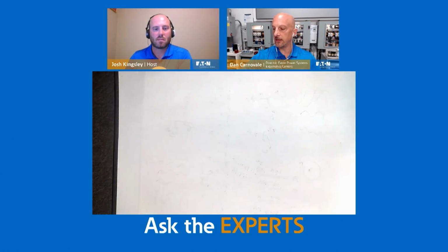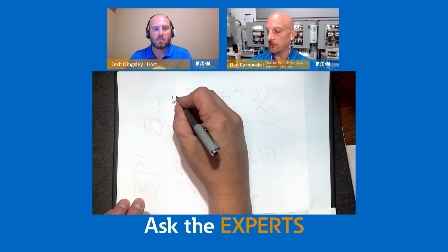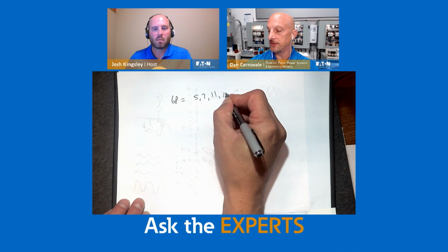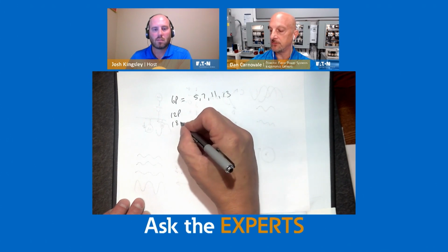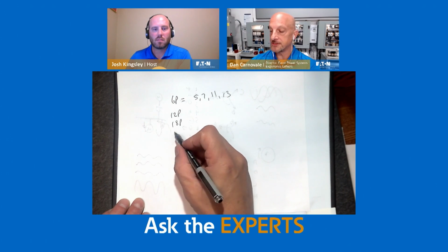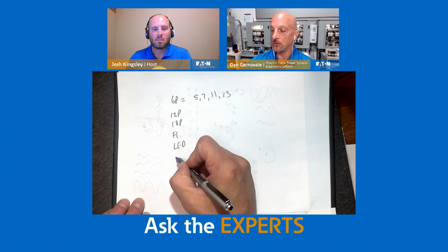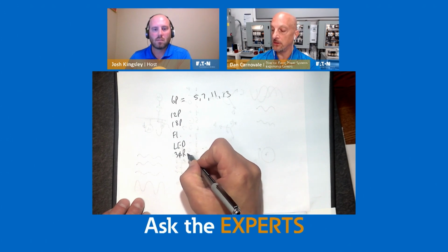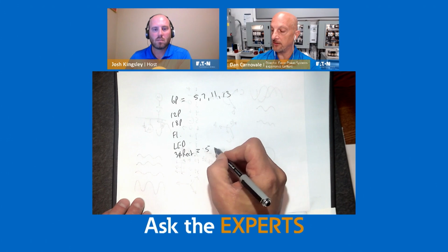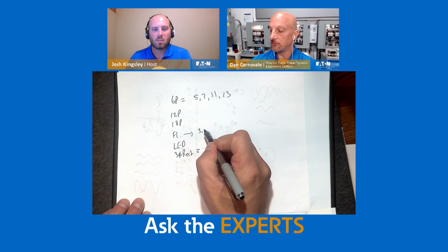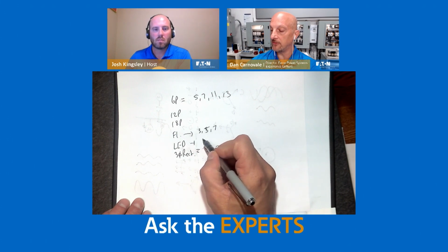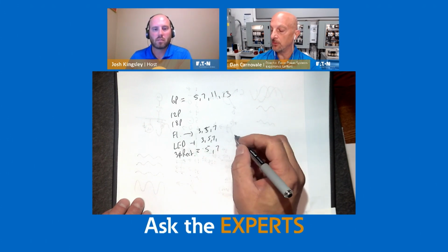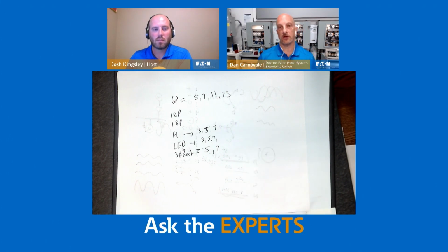And if you look at VFDs, we say six pulse, we already said fifth, seventh, 11th, 13th, 12 pulse, we could figure that out, 18 pulse, we could figure that out. But fluorescent lights or LEDs or maybe a three-phase rectifier for vehicle charging, for example, might have fifth, seventh, whatever. This might have third, fifth, seventh. LEDs might have third, fifth, seventh, but they might be a different spectrum, a different pattern. The nice thing about harmonics is they're pretty predictable in terms of the characteristic harmonics, meaning the signature associated with each type of harmonic. So hope that helps answer the question a little bit.